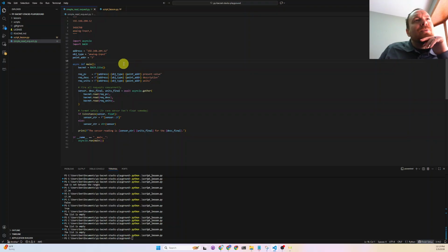I think another thing worth mentioning, which is nice in Python, is you don't really have to get into how BACnet supports all these different primitive data types, because BACpypes and BAC0 running under the hood convert it to anything you see in Python world, which was what we talked about so far: strings, floats, and integers.